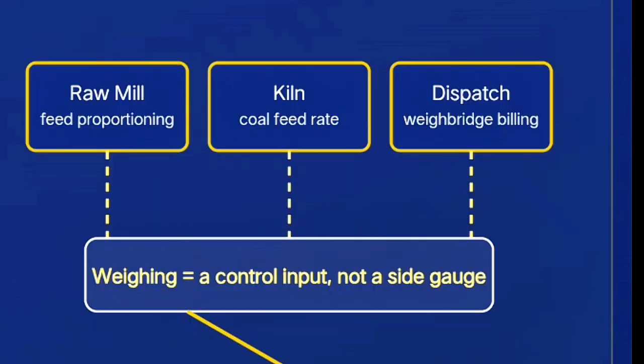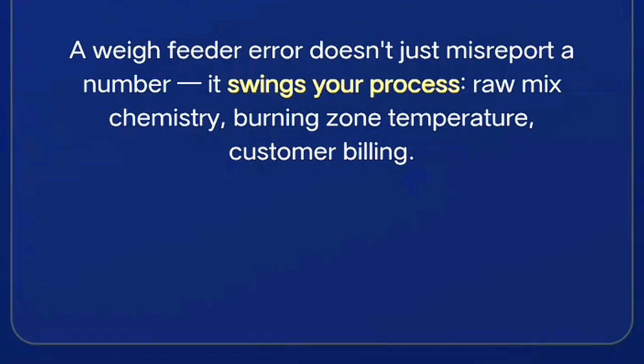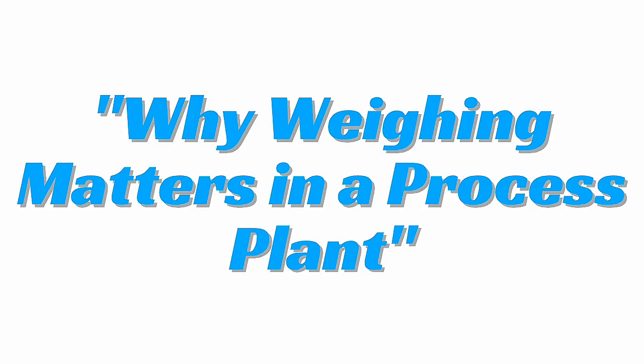Your dispatch weighbridge decides what gets billed to the customer, and that number is legally and commercially binding. So when we say weighing instrumentation, we're not talking about a scale in a warehouse. We're talking about a real-time process measurement that feeds directly into control loops and into your P&L.